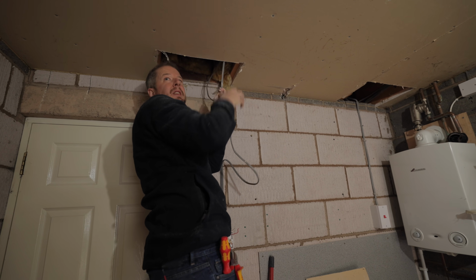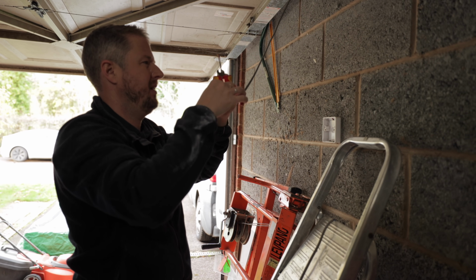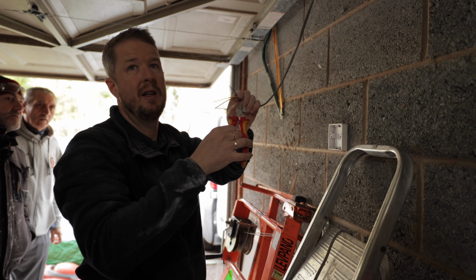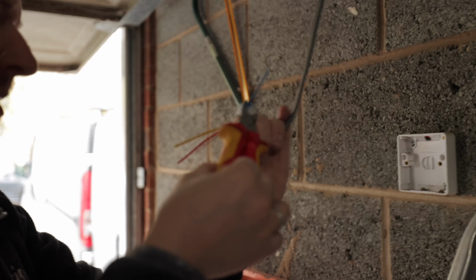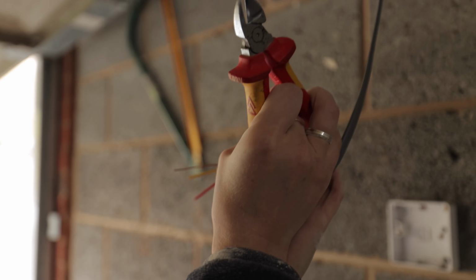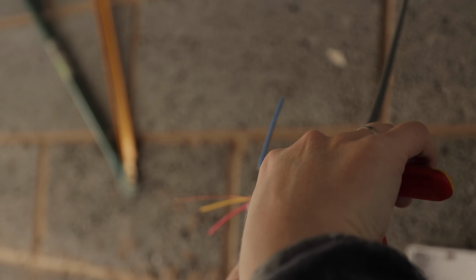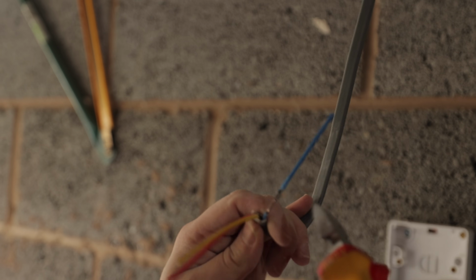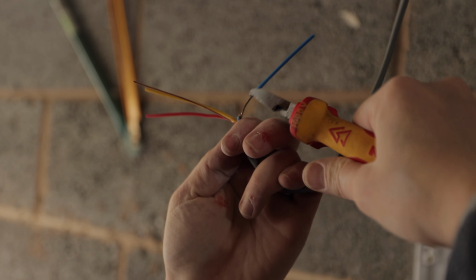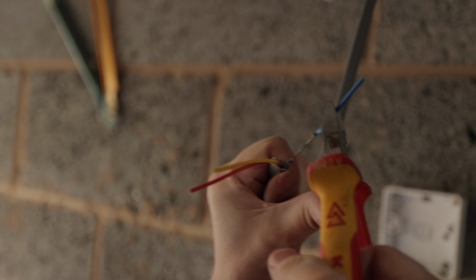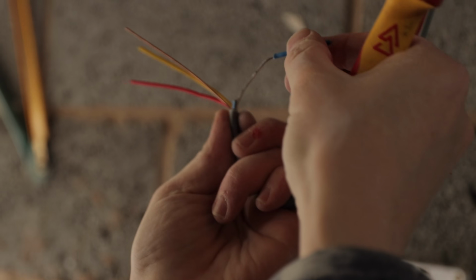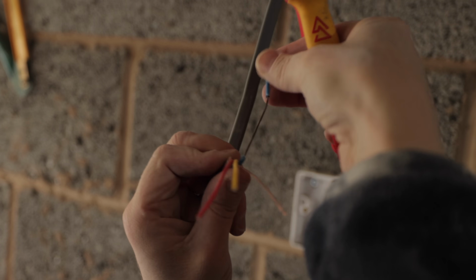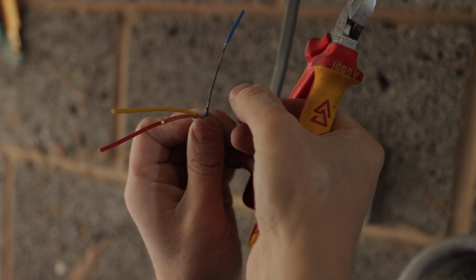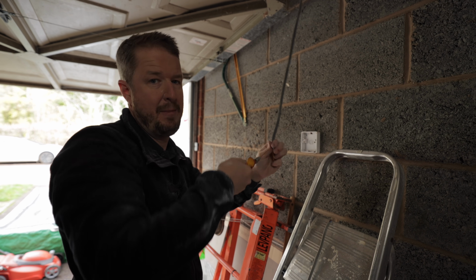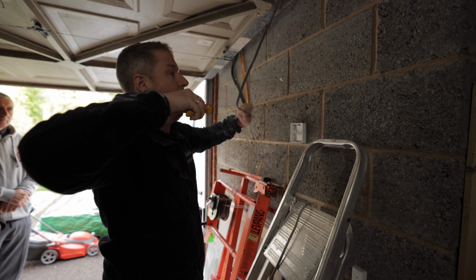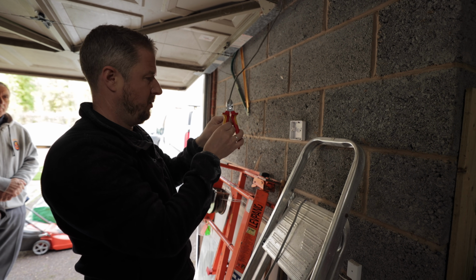We're going to pull the cable out. Oh, it's not very nice, this cable at all. I think that might be the issue, you know. Yeah, look at that, look at that. So, see how blackened that is inside there? I'm stripping the cable back and it's all black inside. That is a dodgy cable. So, I don't know whether the entire cable is faulty and it's been like tracking along the insulation or something. Look at that. It's completely like corroded almost. I feel like it might actually be a manufacturing fault on the cable that's caused the issue.